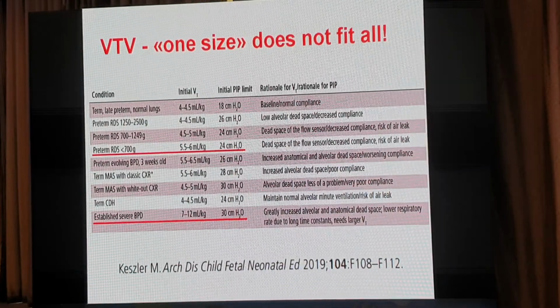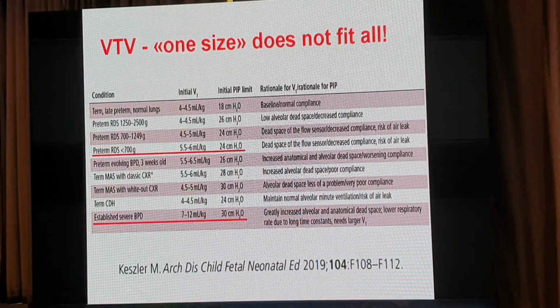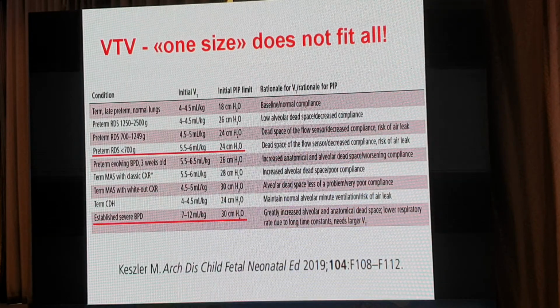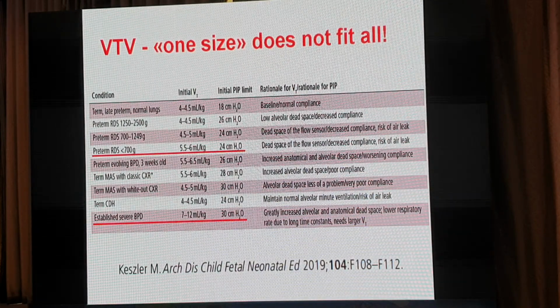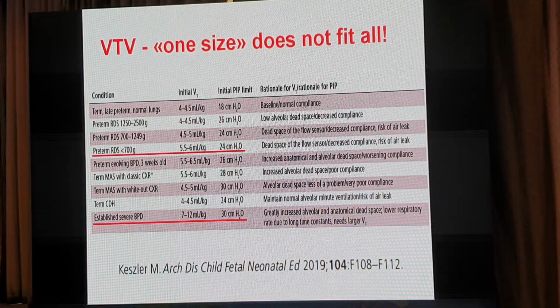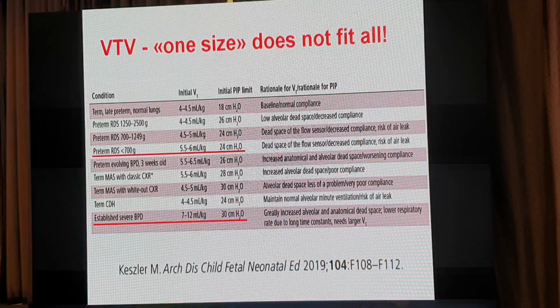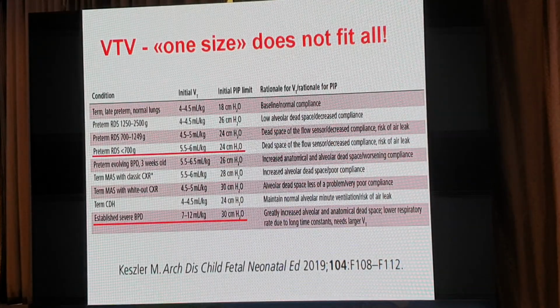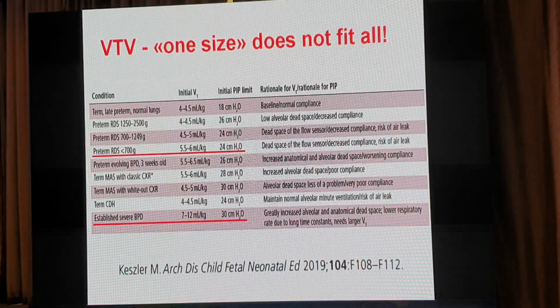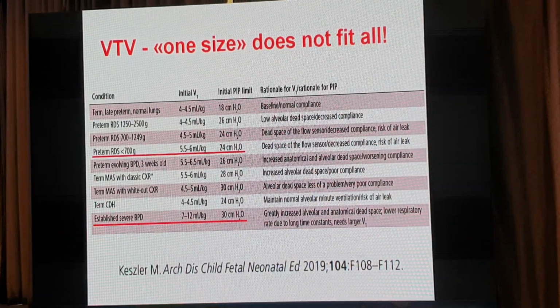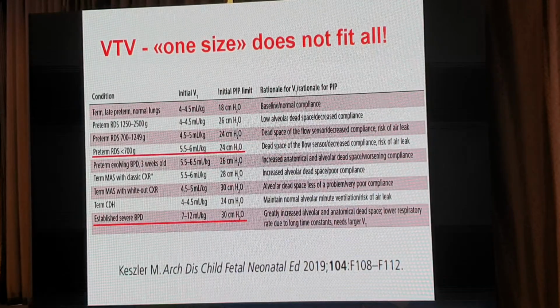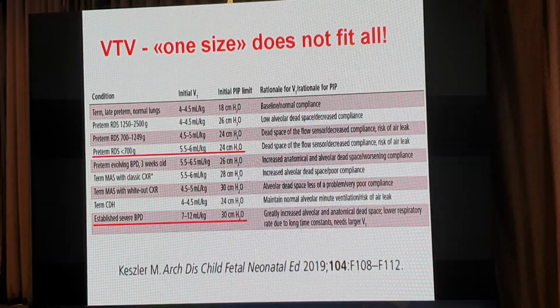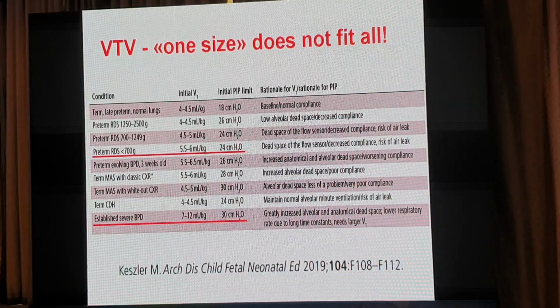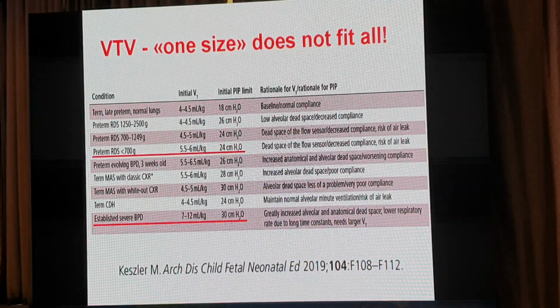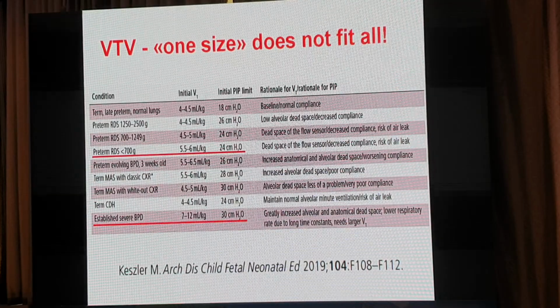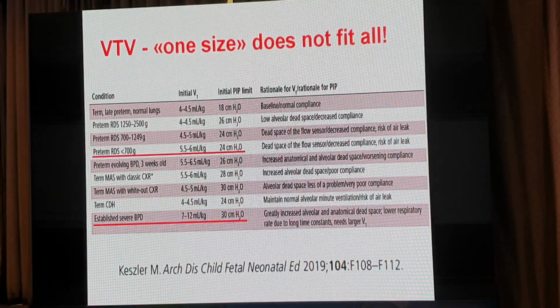He has suggested different volumes to select based on the condition of the infant. What's interesting and a bit counterintuitive is that the smallest infants need somewhat larger tidal volumes, because the dead space of the flow sensor contributes relatively more in very small infants of 600-700 grams. Most people think that because the baby is very small, they should be gentle and use very low tidal volumes, but in contrast, you actually need to pick larger tidal volumes for the smallest ones to achieve normal ventilation.